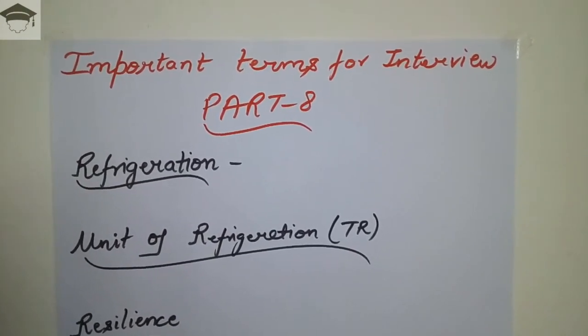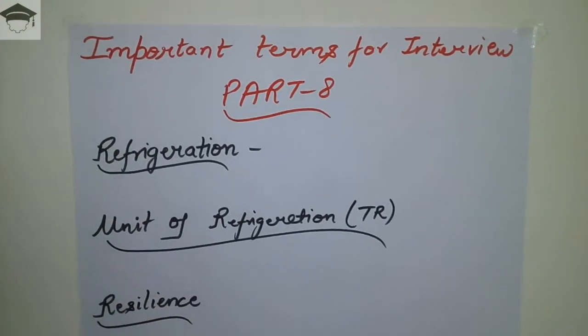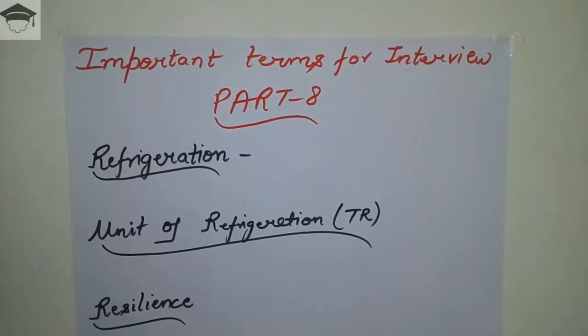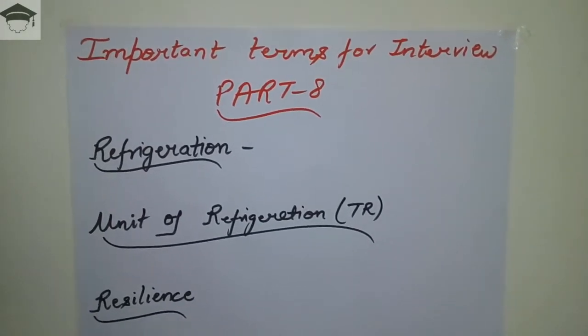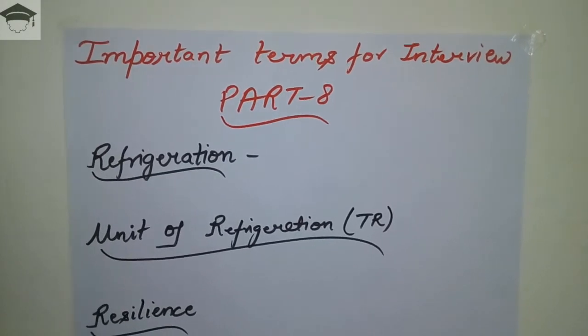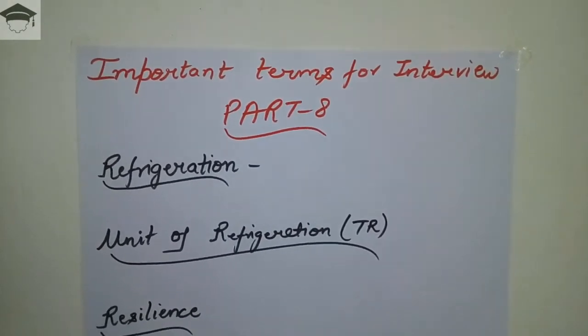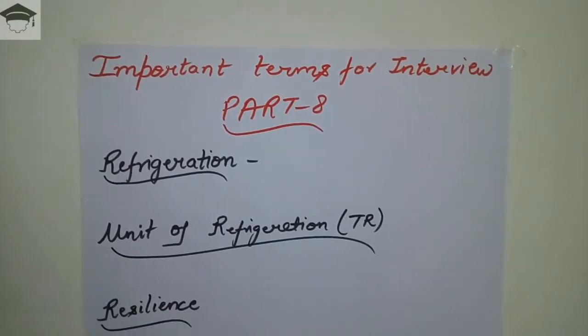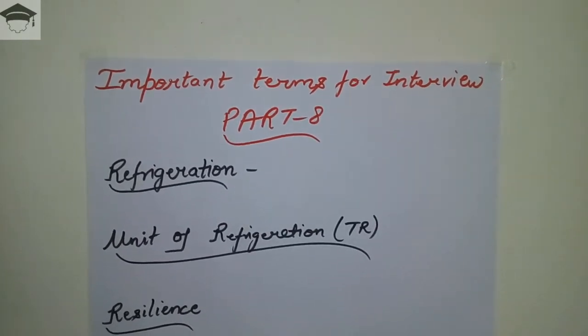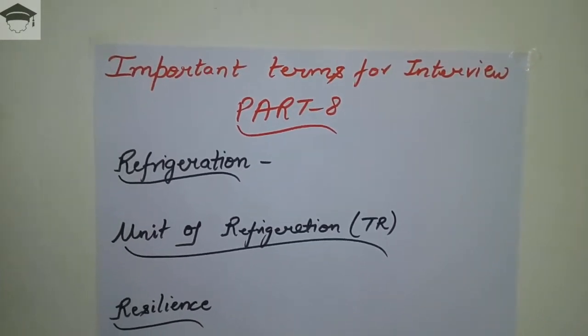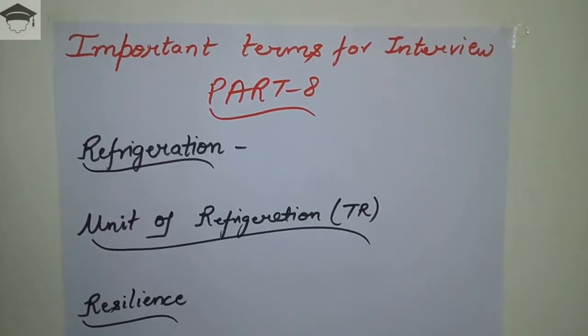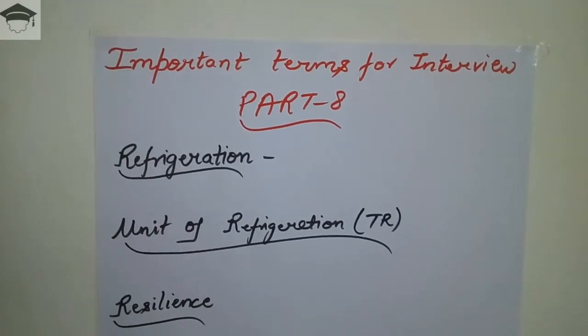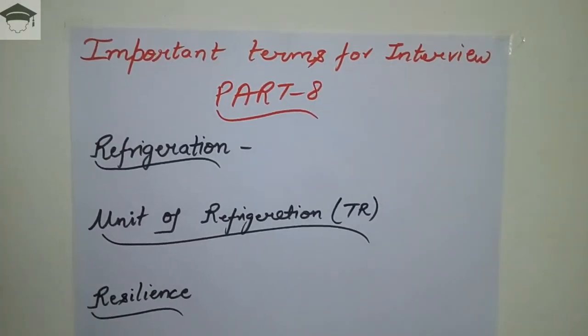The playlist also covers all videos on refrigeration as well as air conditioning. Now, the unit of refrigeration is ton of refrigeration, also known as TR. One ton of refrigeration is equal to 3.51 kilowatts, which is equal to 210 kilojoules per minute. One TR is defined as the amount of heat required to be removed from one US ton of water at 0°C to convert it into one US ton of ice at 0°C in 24 hours.